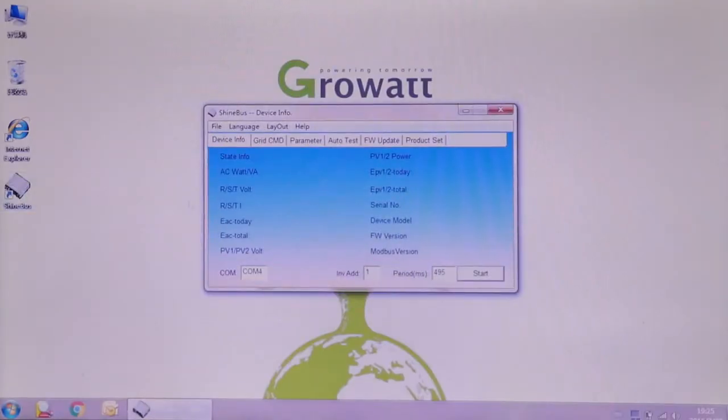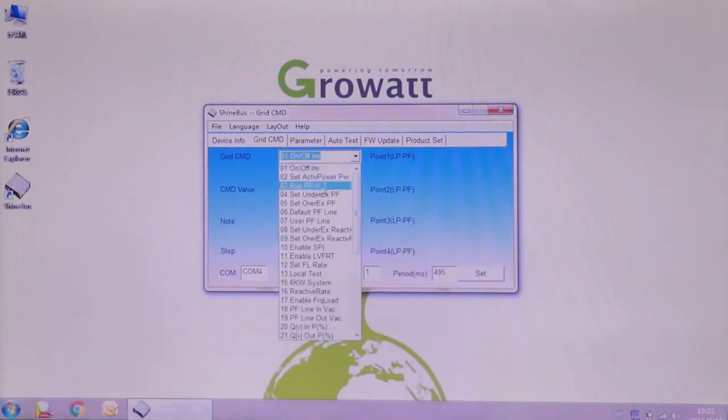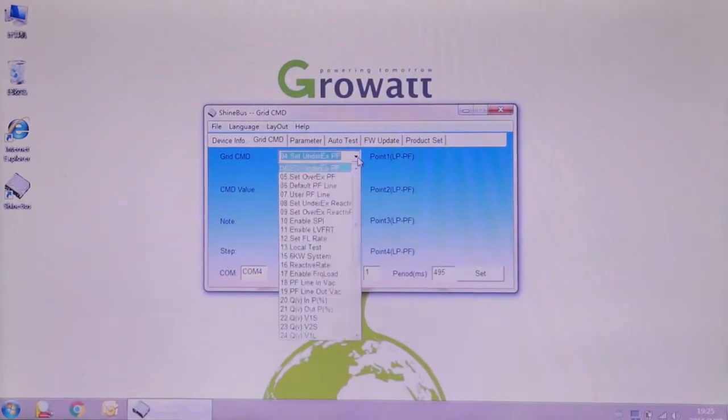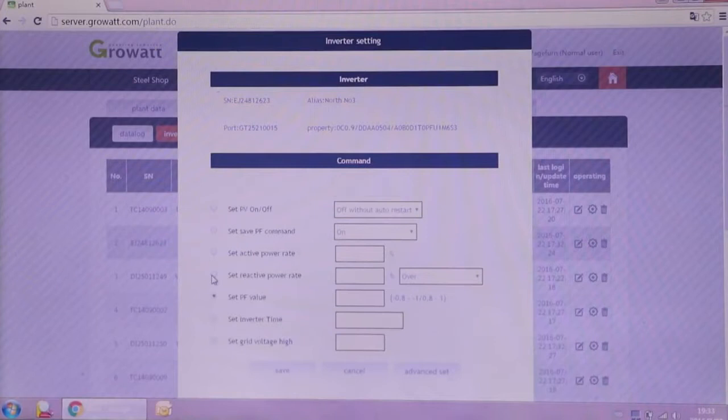The MTLS series inverter also integrates power factor adjustment and reactive power control functions. The values can be preset at the factory on request, or adjusted using ShineBus software after installation. Remote adjustment via the Shine server web page is also an option if there is a Growatt Wi-Fi module for monitoring.